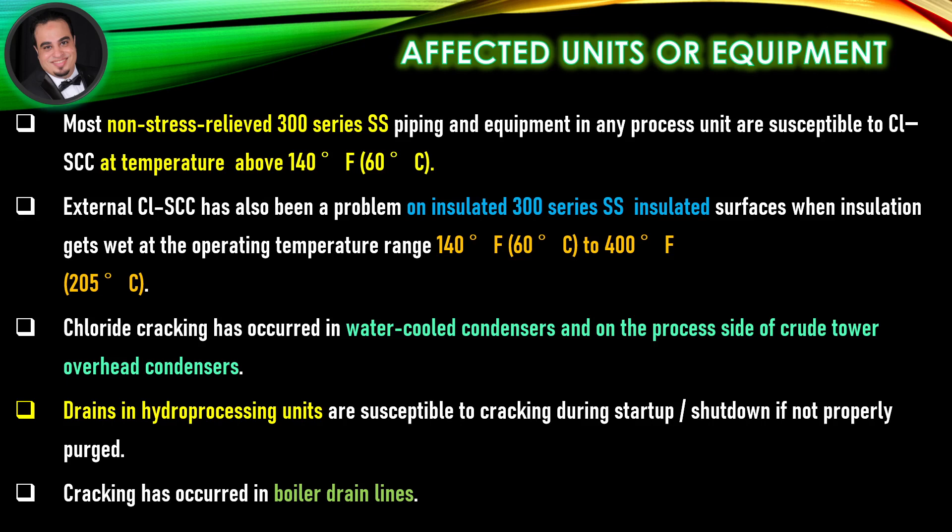Chloride cracking has occurred in water-cooled condensers and on the process side of crude tower overhead condensers. Drains in hydroprocessing units are susceptible to cracking during start-up and shutdown if not properly purged. Cracking has also occurred in boiler drain lines.